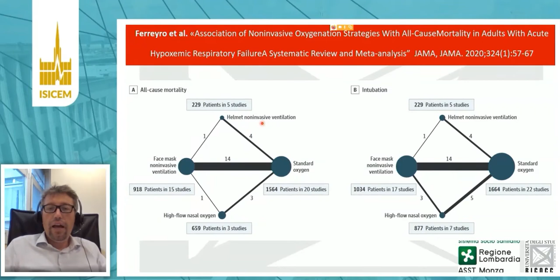And so what are helmets? Basically, helmets are what they are: a hood, a plastic tent with two holes, one for the gas inlet and one for the gas outlet. Now, the point is what you connect to the helmet. As we are delivering non-invasive ventilation, you would be tempted to connect a ventilator, which is something we can do, as I will show you, but it's not what I would recommend to start with.